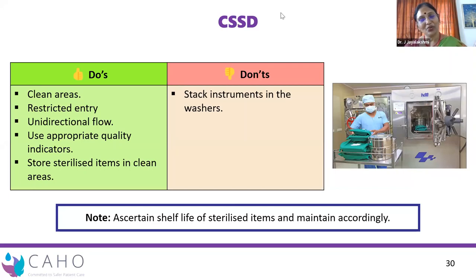Once a day is best, or at least once a week, you should use an appropriate biological indicator, processed after the sterilization process. You also reclaim it at the appropriate temperature. For example, a Geobacillus stearothermophilus indicator requires an incubator set at 56 degrees centigrade.